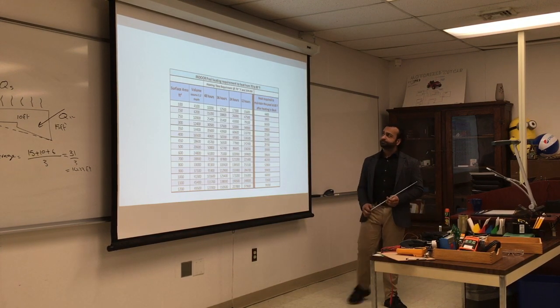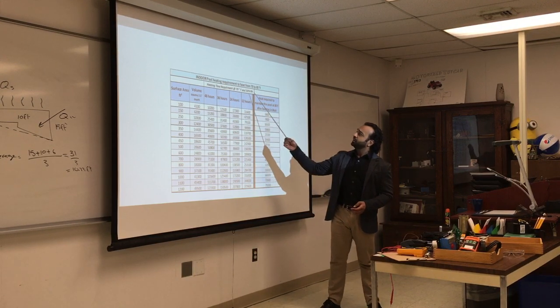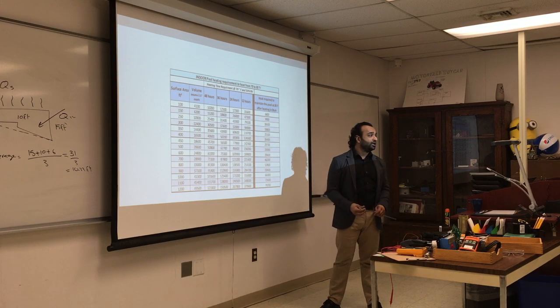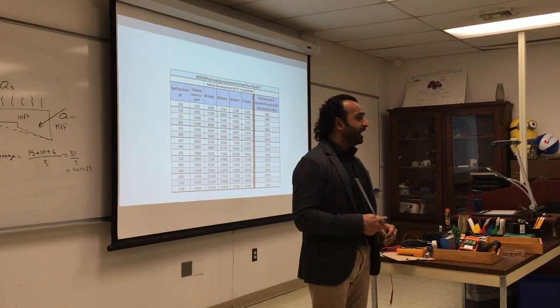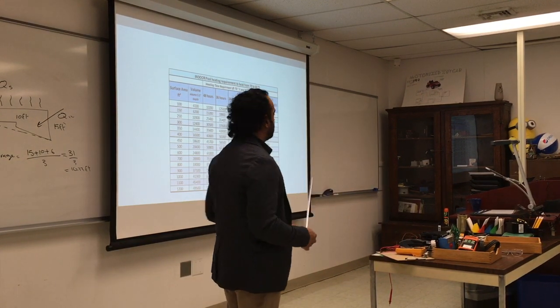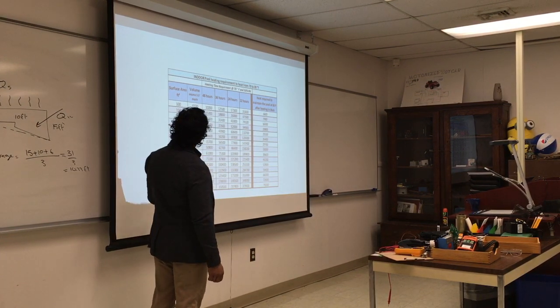Indoor is different. Some stuff goes into it, like heating time requirement, keeping the inside around 70, and also relative humidity. You don't want the pool to humidify the entire location. If you go to indoor pools like the YMCA or some gyms, they have to think about that a lot, because the pool is going to evaporate, and if the air gets saturated, it's not very comfortable. And again, this time I'm going to go with the surface area and volume. Again, assuming 5.5 depth, and the time required to heat the pool, then how much is needed to maintain it.